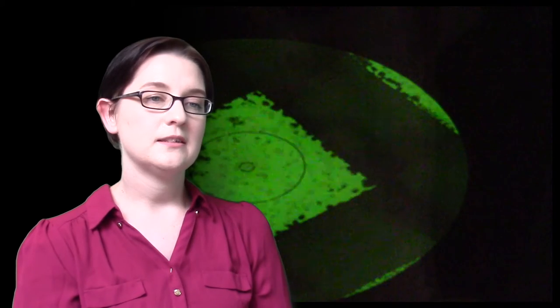Images can be recorded with film, or now more commonly, with a digital camera or a direct electron detector that can be side or bottom mounted. The control panels are used to adjust beam intensity (adjusting the condenser lens), focus (adjusting the objective lens), magnification (adjusting the projection and intermediate lenses), and eucentric height and various alignments.